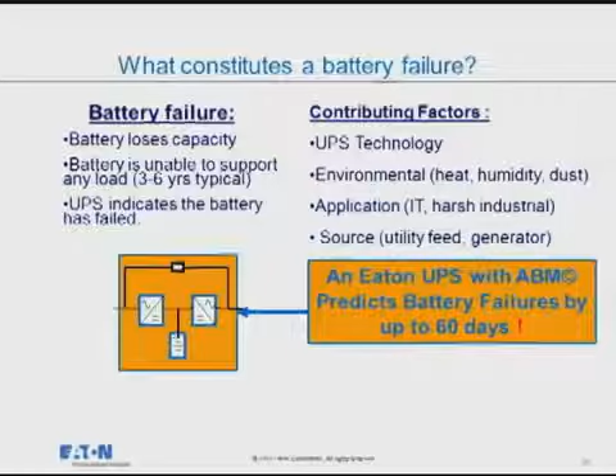The other piece that does it is charging, right? What I do - remember, I have a depleted battery, I put charge into it to get the electrolyte working until I'm at 100% utilization. But then if I continue to charge the battery, what's called floating, what I'm actually doing is continually trying to put more charge into an already 100% charged battery. It's not an efficient process, and I'm losing a sliver of capacity in that.